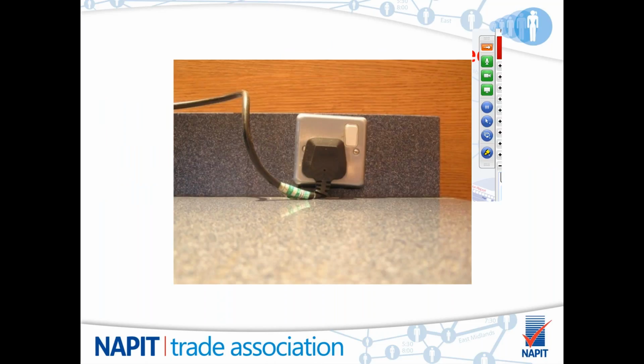Here we've got an issue. Obviously, it's pretty evident that this socket is installed within the worktop too close to the surface. There is obviously damage that could be caused to the flex. If this is the case, then obviously we're looking at coding it as a... Well, I mean, is it causing damage? If it is, then maybe code 2. But in this case, this is open for interpretation for yourself to make your own mind up. C3 probably in this situation, yeah. Regulation 553.1.6 of the regs states that the socket should be high enough to withstand damage to the flex and the plug top.